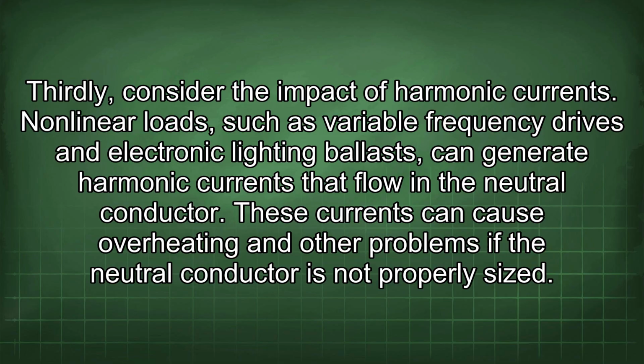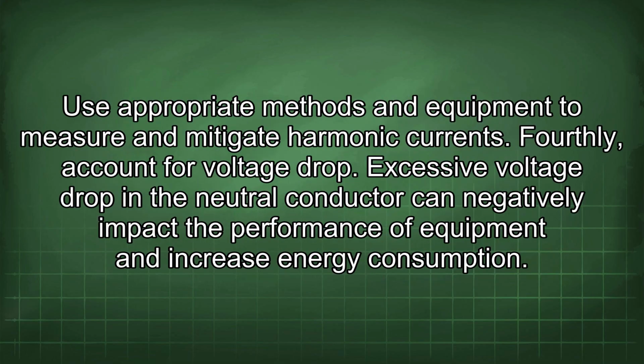Nonlinear loads, such as variable frequency drives and electronic lighting ballasts, can generate harmonic currents that flow in the neutral conductor. These currents can cause overheating and other problems if the neutral conductor is not properly sized. Use appropriate methods and equipment to measure and mitigate harmonic currents.